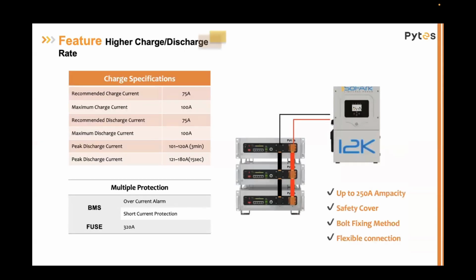One thing that's very unique and really great about this design is that with our bus bars rated for 300 amps, we're allowed to take one whole stack and directly hook it up into a Sol-Ark 15K. This is great because it cuts out the need for a third-party battery combiner and just makes the communication so much simpler when using a Sol-Ark 15K with one of our stacks of batteries.